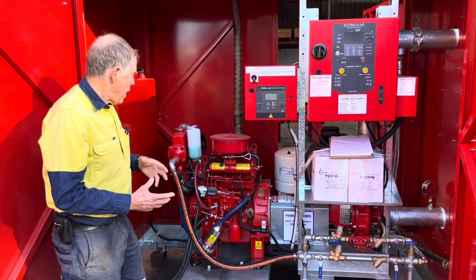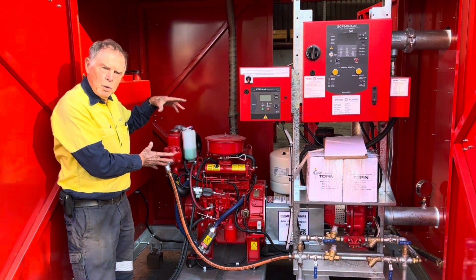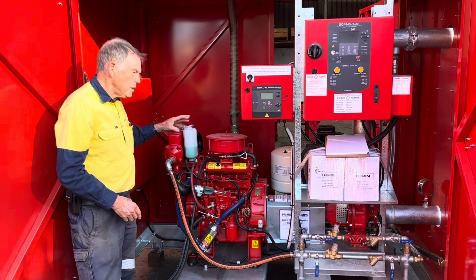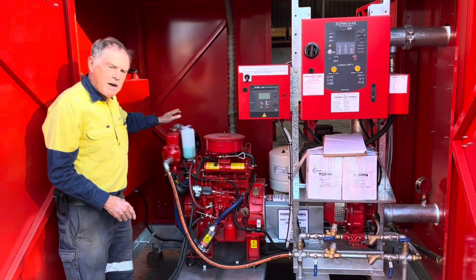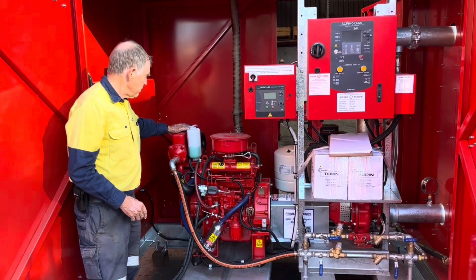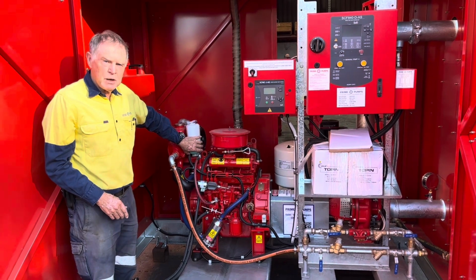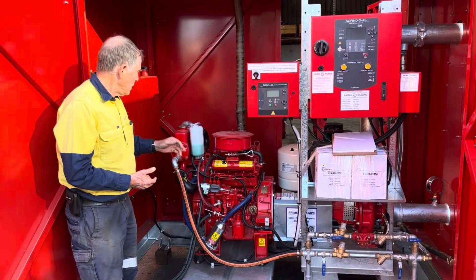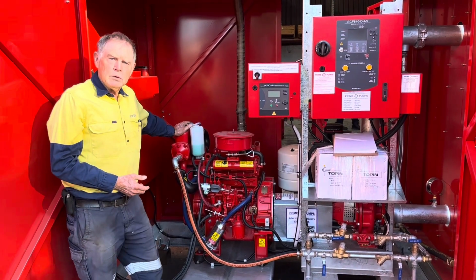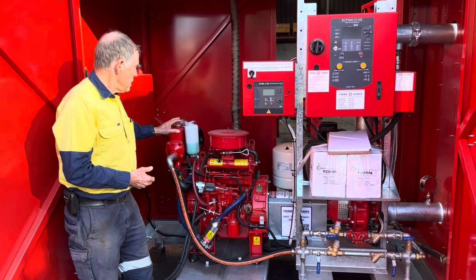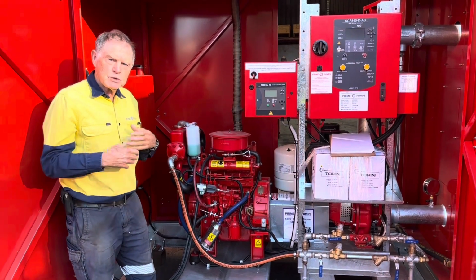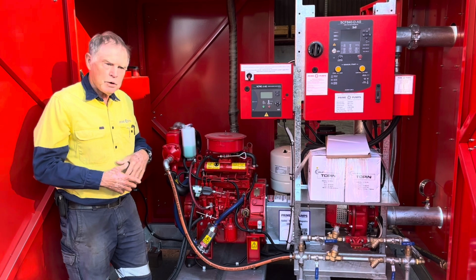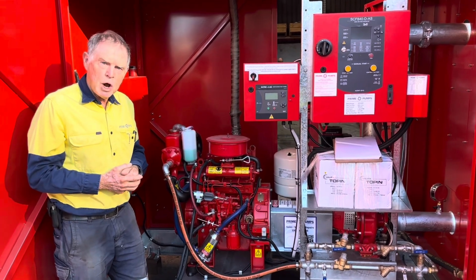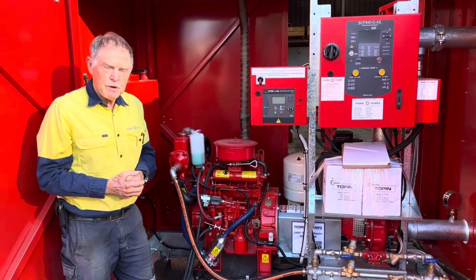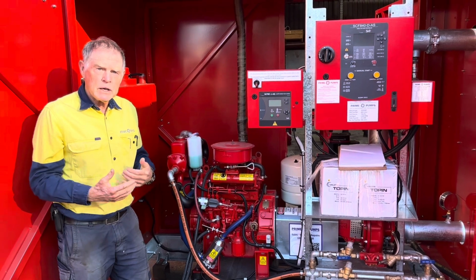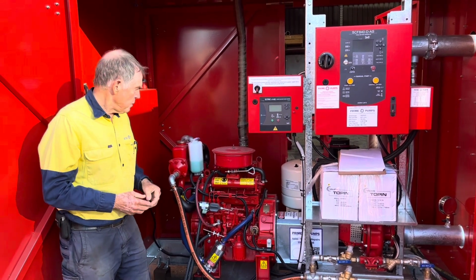What we need to do now is think about the water, what we'll call the conditioned water within the engine. So instead of having a radiator, we have a heat exchanger. The heat exchanger has a header tank, which is the same as what you'd find on your car, and we never put straight water in a modern fire pump engine - it's always got to be conditioned water. It's got a whole lot of chemicals in there to prevent corrosion and most importantly to prevent freezing when we're operating in areas that operate below zero.